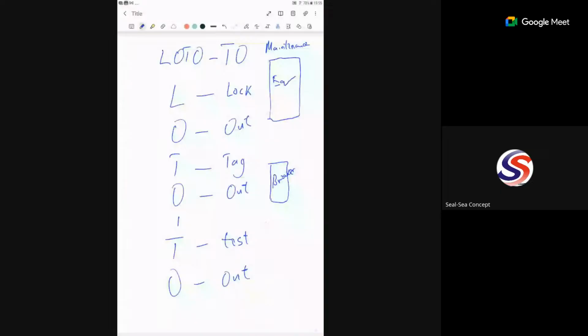Both you and the personnel carrying out the LOTO process go together to the breaker that supplies the equipment, and they remove it. The lock, the tag, and the paper you filled out together make up what we call the tag.